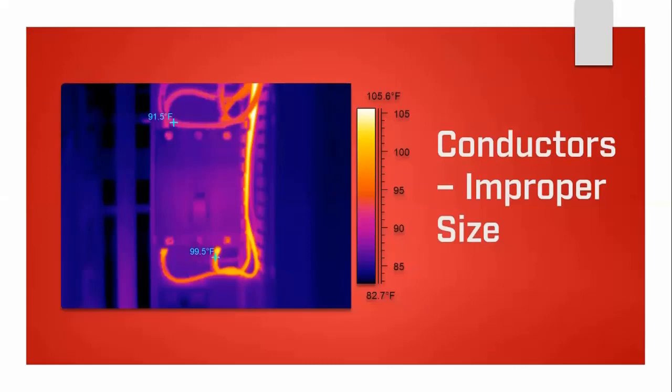Poor installation: conductors or cables of the wrong size. This is a 40-amp molded case circuit breaker used as a disconnect on a machine. The breaker is three-phase but only two phases are used. Notice the heat on the load side compared to the line conductors — a sign to look deeper. In the infrared image, the load conductors appear smaller than the line conductors: line diameter is 6 and load diameter is 12. The machine wiring wasn't part of the original survey, but as covers were removed for access in the area, it was noted in the report.